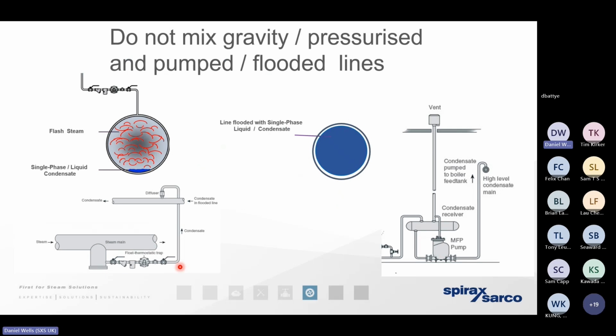Now, we have also mentioned that in certain cases, the condensate will be brought back to the boiler house under pressure. If there's enough residual pressure in the condensate pipework, the condensate has generally got its own motive energy. But because of that pressure drop within the system, we need to allow for that flash steam, that larger volume, to exist. But on those occasions where we need to pump the condensate back, whether it be electrically or mechanically, we can only pump the condensate as a liquid. So we need to vent that steam away. So there is going to be a slight inefficiency we need to take into account there.